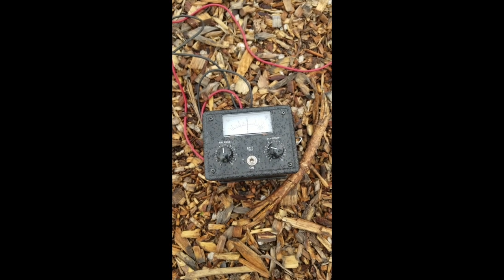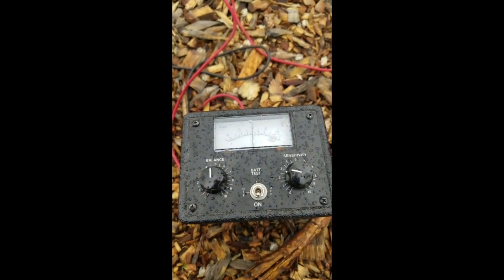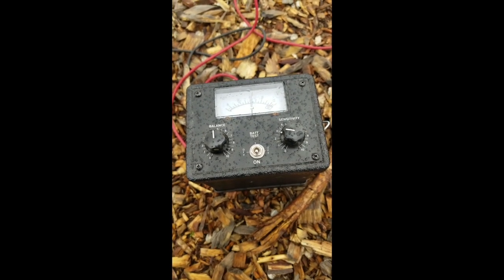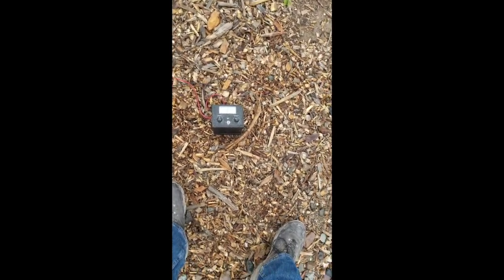So it's still telling me the black probe's closer, but it's a lot smaller reading. That means I'm getting closer to that null point. So I'm going to move it again another foot or two. Let's see what I get here. That meter's barely moving on that initial deflection. That's pretty close to a null point. Once you get that null, the real simple thing for me to do is just pick one of the probes. I don't care which one. I'm going to move the red one, and I'm going to split that difference in half. So I've got about 6 feet there, 7 feet. So I'm going to take this red probe, put it at my midpoint between the two, over the top of my cable route. See what I got here now.